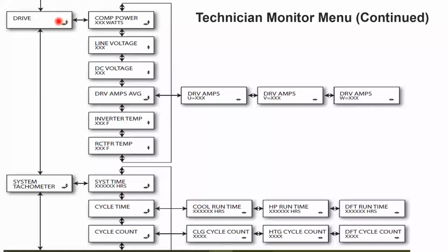So now from drive, you press right, we can see our compressor watts, our incoming line voltage, our DC voltage, our drive amps, inverter temp, rectifier temp. So we get into this sometimes, so you can actually compare that DC voltage. From drive, you can scroll down, see system tachometer. So we can see system runtime, cycle count. So a lot of information in this.